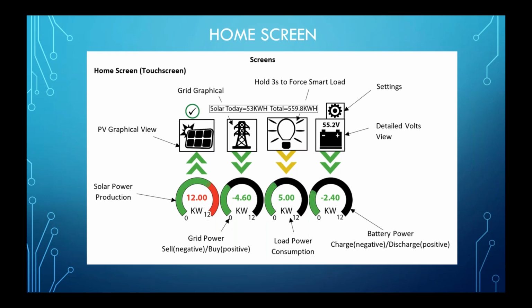So let's take a quick look at the story that this is telling us, because this screen does tell you a story. The solar system is making 12 kilowatts right now. That's a good size solar system. Must be a sunny day in Texas or a sunny day in Texas North. And we're making 12 kilowatts. Bounce over 2, under the light bulb, and you see the load, or the home, is consuming 5 kilowatts. So the Sol-Ark said, all right, I got 12 kilowatts of DC power coming in. I'm going to convert that to AC. I'm going to put 5 kilowatts over here to the home. I'm going to convert some more power to AC, and I'm going to sell power to the grid. So it is selling power to the grid right now, 4.6 kW.